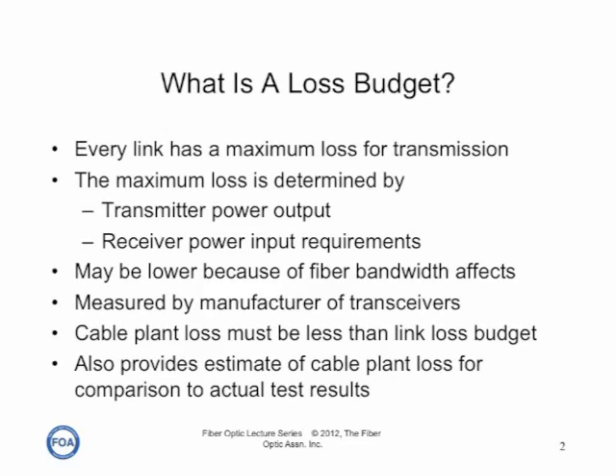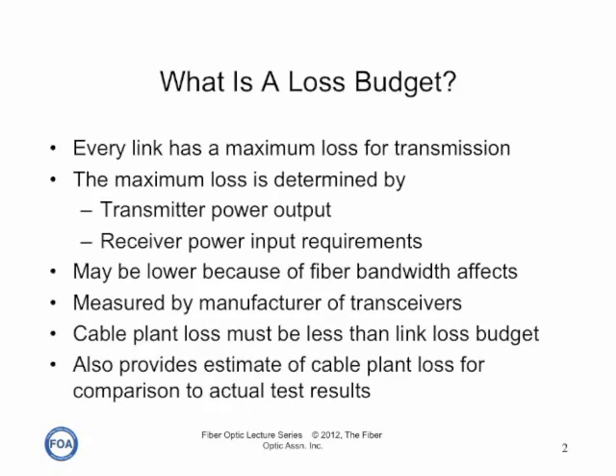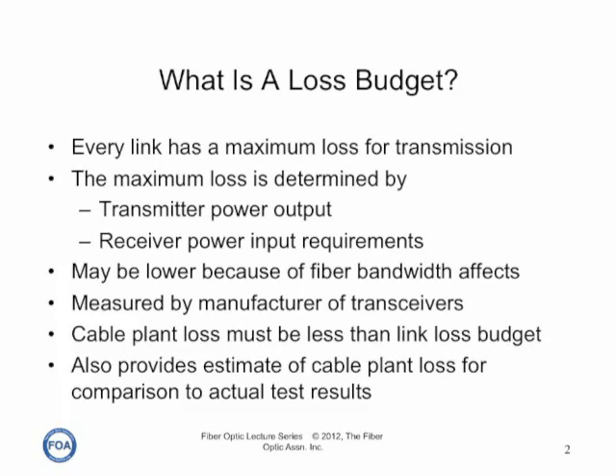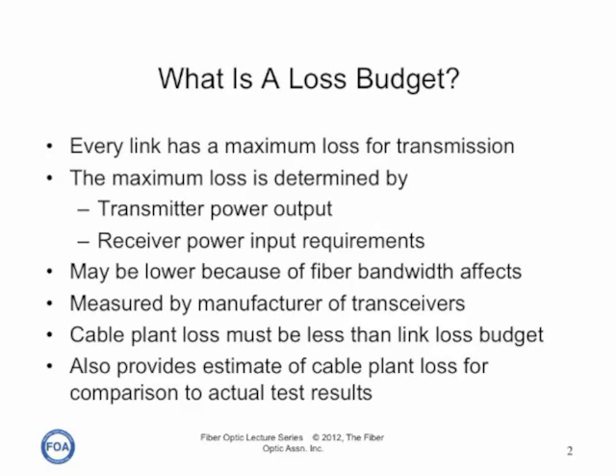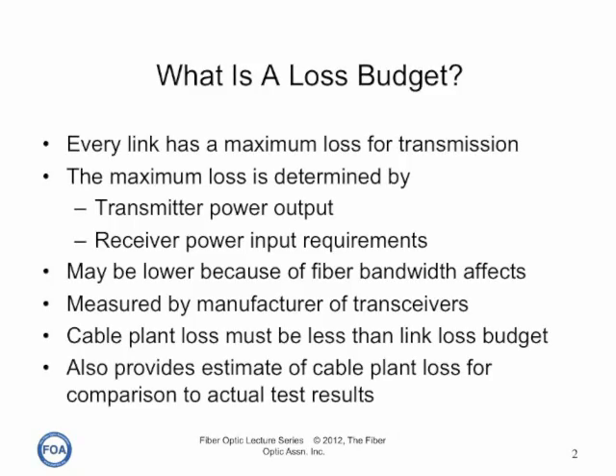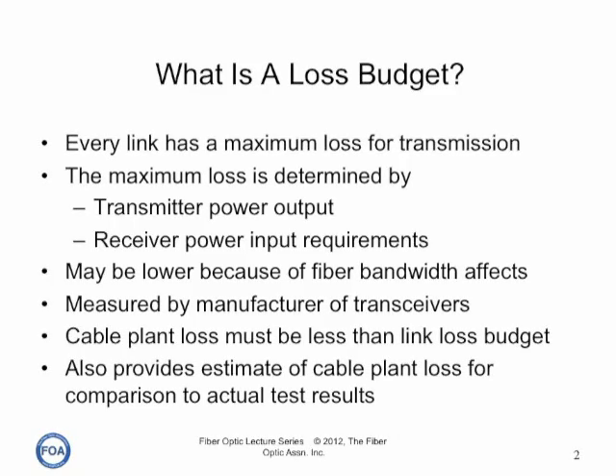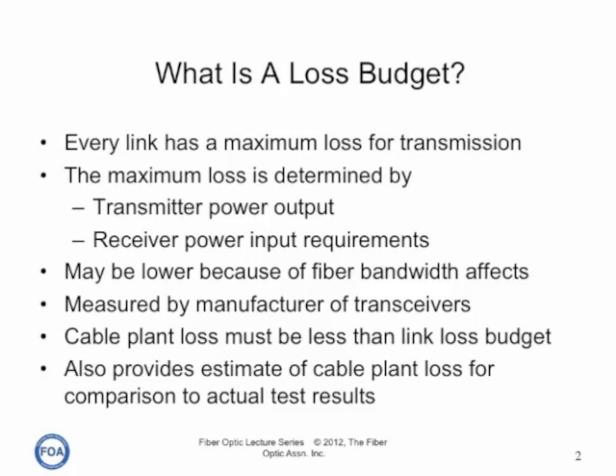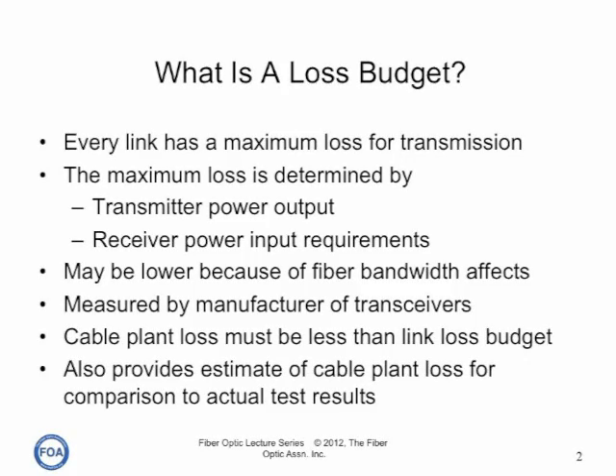A loss budget is a very important specification for a fiber optic link. It determines the maximum loss the link can tolerate for transmission. That loss is determined by the output of the transmitter and the required power at the receiver, although it may be lower because of fiber bandwidth effects on high-speed multimode or long single-mode links. The loss budget is established by the manufacturer of the transceiver, and the cable plant loss that you operate the link over must be less than that link loss budget.